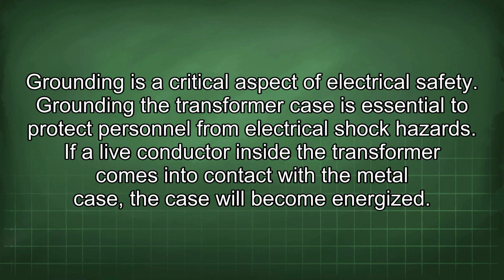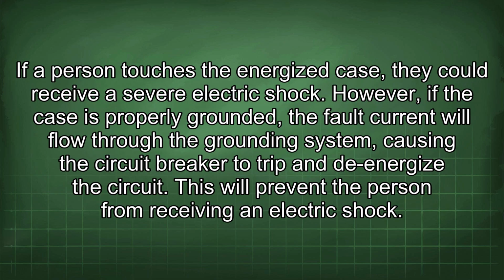Grounding is a critical aspect of electrical safety. Grounding the transformer case is essential to protect personnel from electrical shock hazards. If a live conductor inside the transformer comes into contact with the metal case, the case will become energized. If a person touches the energized case, they could receive a severe electric shock. However, if the case is properly grounded, the fault current will flow through the grounding system, causing the circuit breaker to trip and de-energize the circuit. This will prevent the person from receiving an electric shock.